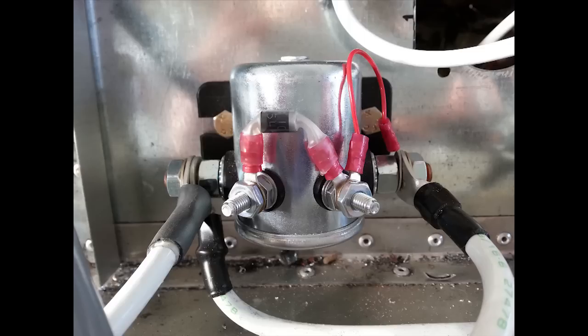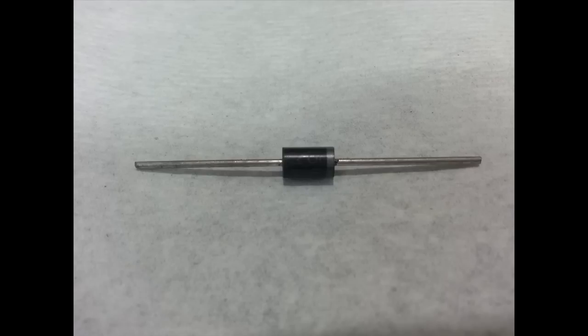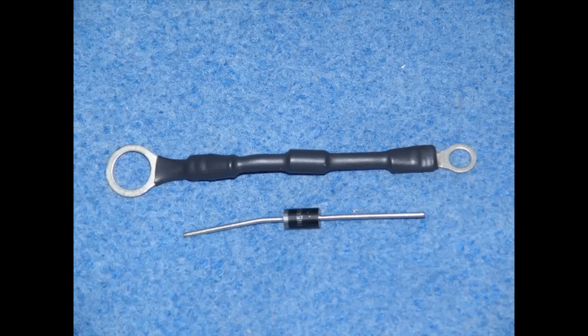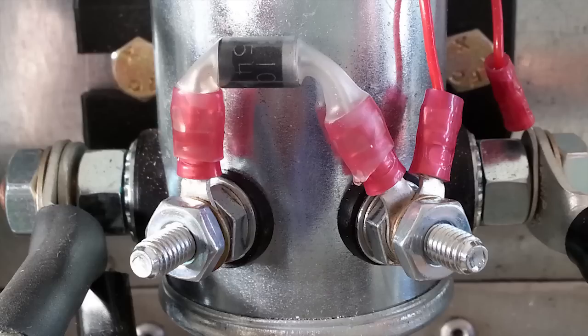Some contactors provide the diode already wired in, many do not. The least expensive way is to purchase a bunch of these diodes, less than a dollar a piece, and then crimp the appropriate ring terminal on the ends so they are easily installed onto the terminals of your contactor. It is wise to insulate the leads of the diode as they expose 12 volts, which should be protected from shorts.